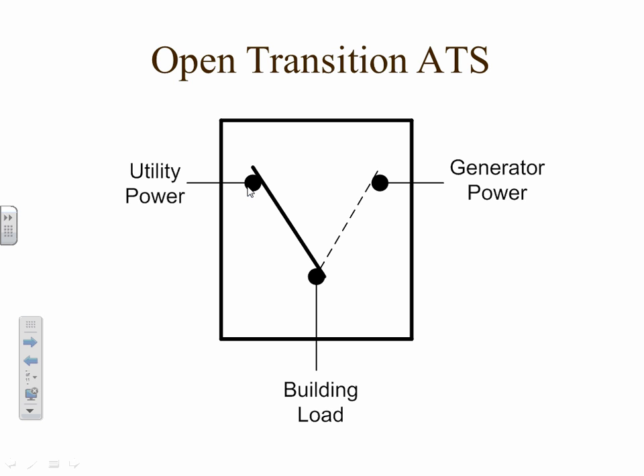Well, you really don't want to be switching back and forth, transferring power between utility and generator set all the time. So they say, okay, on this time delay, let's make it about 30 minutes. And typically, our technicians will set these at about 15 minutes in the field, realistically. And it's waiting to make sure that utility is really back for good, so it's not going to be going off again. So that's a time delay on retransfer.